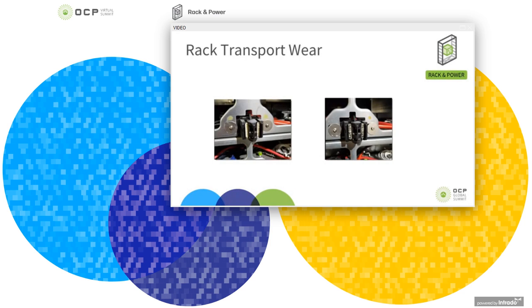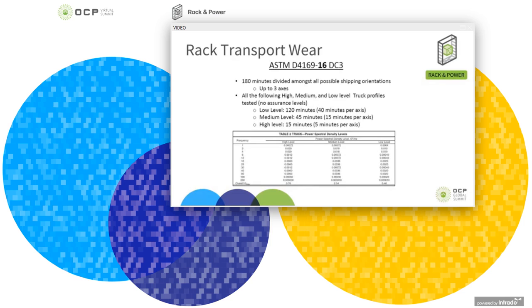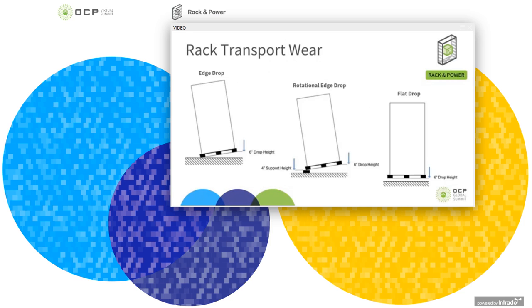From these photos, they're just simply showing the lubricant applied to the connectors. And for reference, we wanted to include the ASTM spec used in the transportation testing. This illustration is showing the definition of the drops. Starting from the left, the edge is on the floor, and the opposite edge is raised 6 inches and then released. The rotational edge drop in the middle picture is 4 inches on the support height and then drops 6 inches on the other edge. And the flat drop is 6 inches directly off of the floor, dropping straight onto the floor.